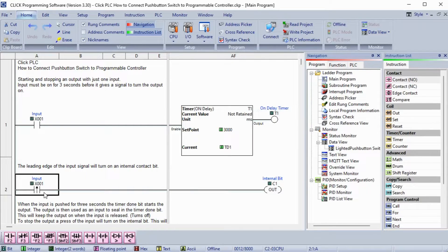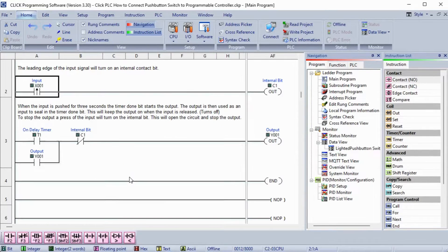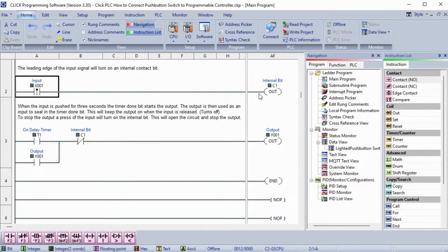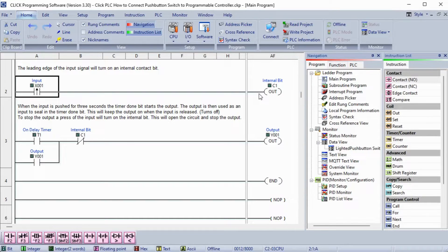Rung 2 will look at the leading edge of the input signal. This will trigger an output for one scan of the PLC when the input transitions from OFF to ON. This will then turn ON an internal bit, indicating that the input has been pressed.